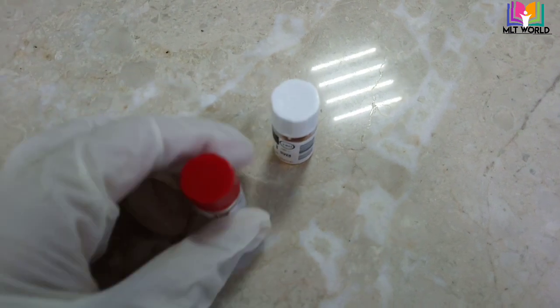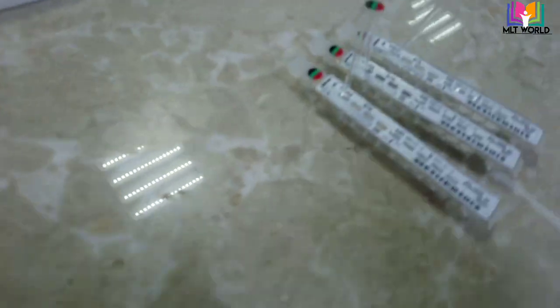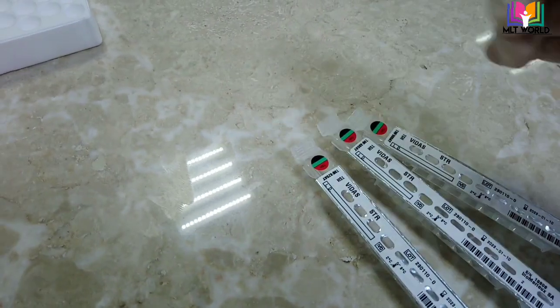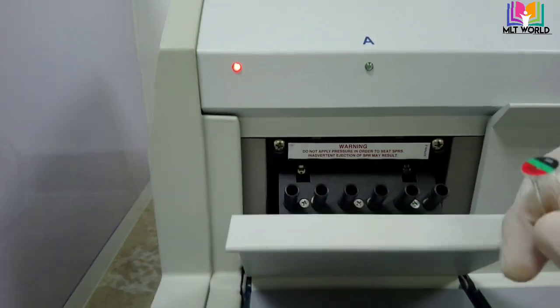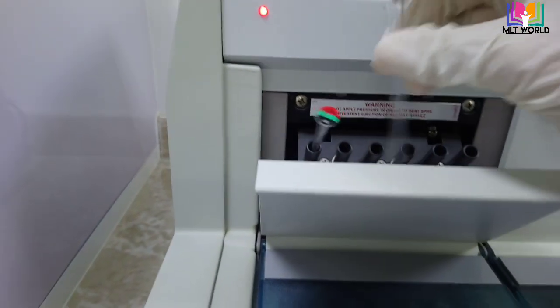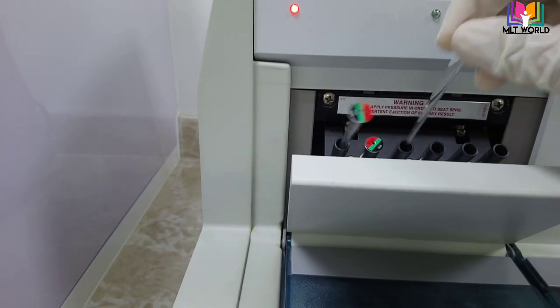After that we will keep the strips of the required test. For example, this is the TSH, we will keep the strips in the machine. Now these are the three strips and the SPR; we will keep them in the machine in the assigned position in the assigned section. As you can see, section A, position 1, 2, 3. And after that we will add 200 microliter and we will do the calibration.